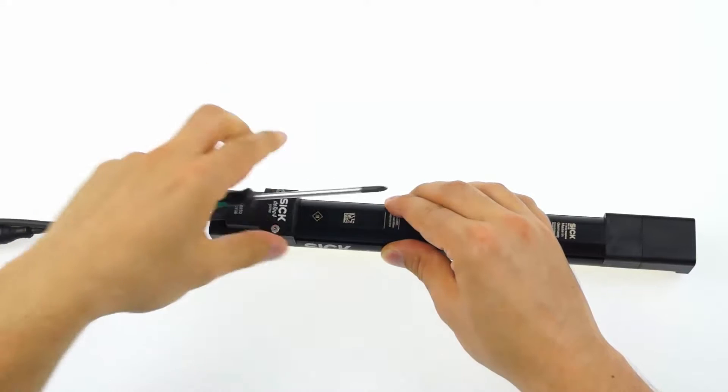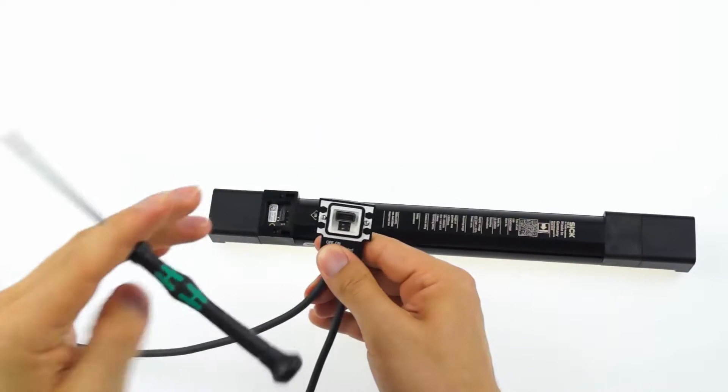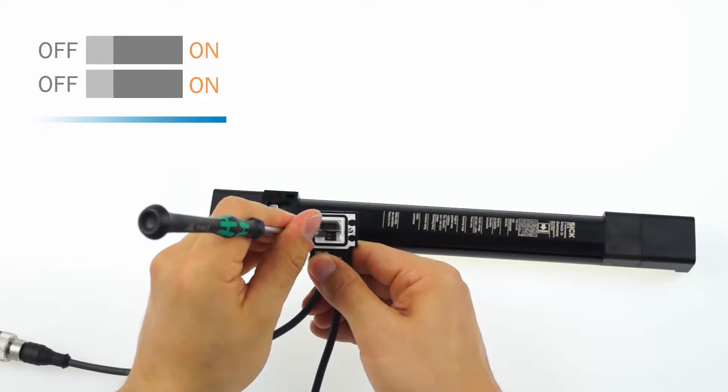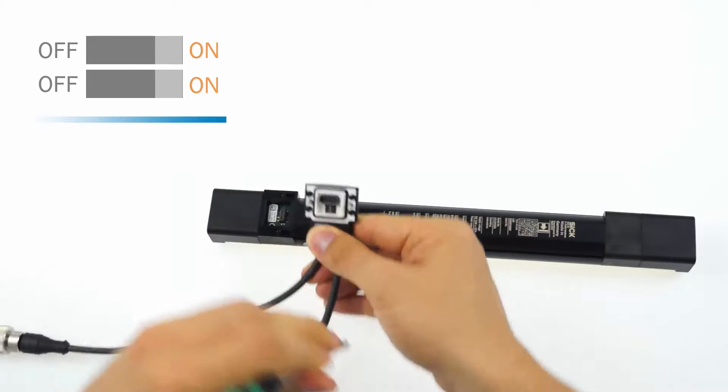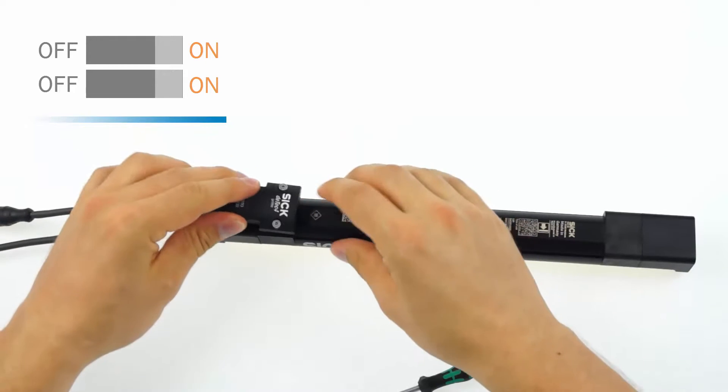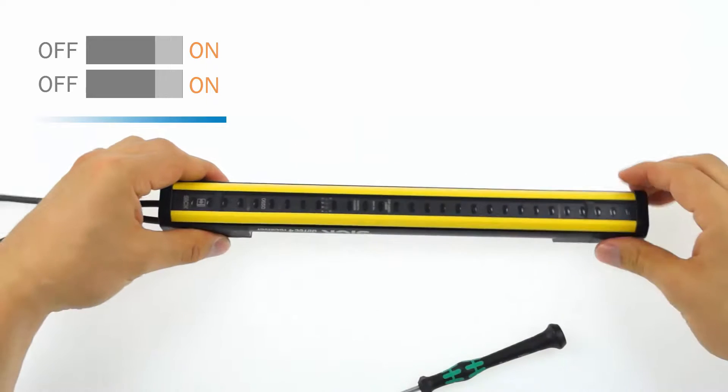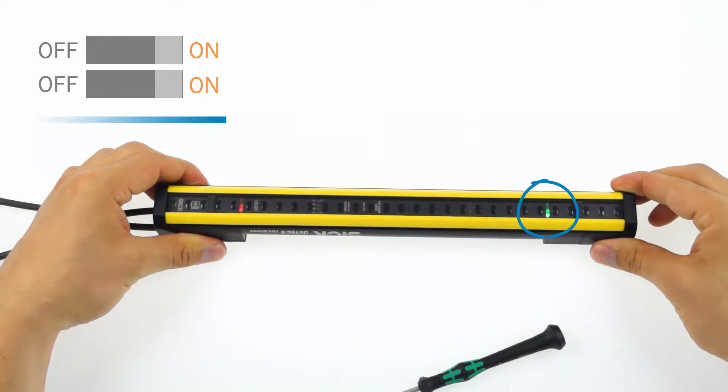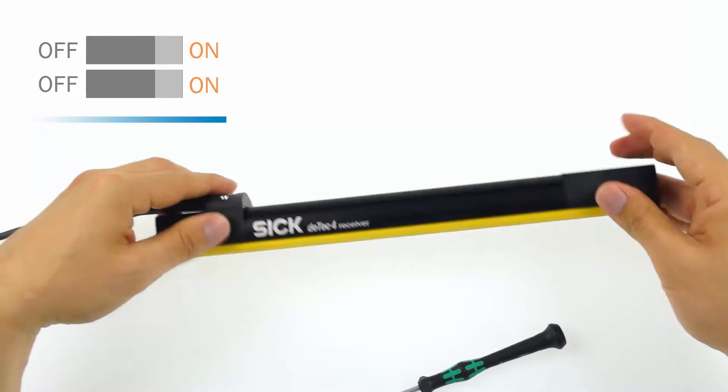In the first step, detach the system plug. Set both of the DIP switches to ON and put the plug back on the device. Switch on the power. The field LEDs are flashing green and yellow now. Disconnect the device from the power supply within 10 seconds.